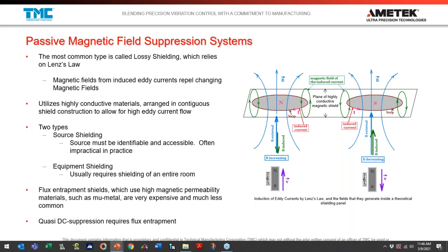One of the key limitations of lossy shielding is that it relies on a changing magnetic field to generate eddy currents, so it becomes less and less effective at lower frequencies. Once you get to DC and quasi DC, lossy shielding becomes very ineffective. For DC shielding, you need to move to flux entrapment shielding using high magnetic permeability materials like mu-metal. Mu-metal, due to its high permeability, sucks in and holds magnetic field lines — magnetic fields prefer lower-energy environments and are drawn to high-permeability materials. Flux entrapment shields are extremely expensive and usually not installed due to cost.